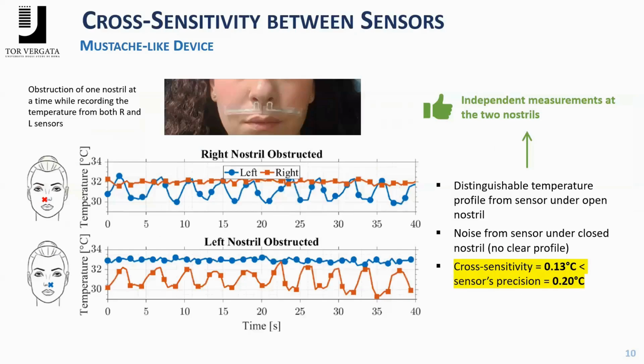This is an important topic, the cross-sensitivity. It means each sensor should measure only what is coming from its own nostril. So we close a nostril and then measure both, and vice versa. And you can see that here, for instance, the flat one is for the closed nostril, and the other one for the free nostril. So we can say that the two sensors are reasonably independent. The cross sensitivity is 0.1 degree, which is less than the sensor precision, so we will not really recognize it in a practical application.